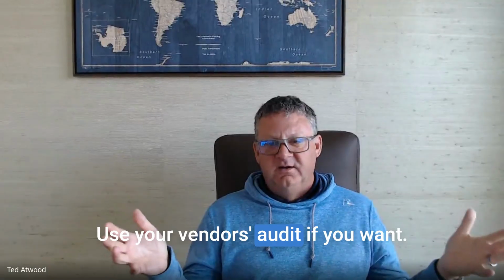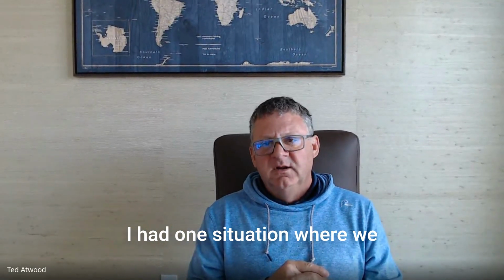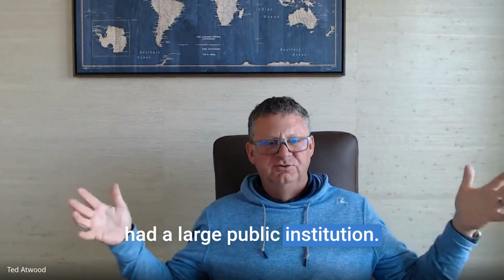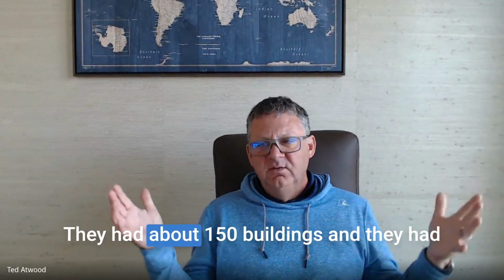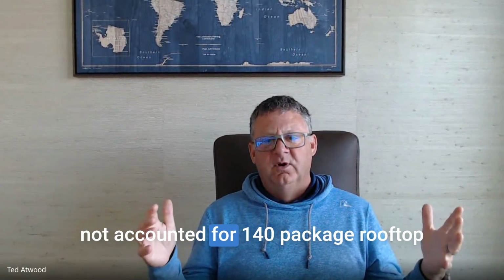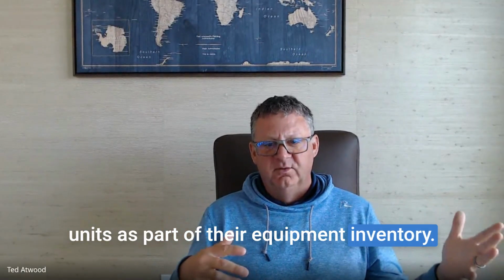You use your vendor's audit if you want. You start with that. Say, okay, we've got your list. I had one situation where we had a large public institution that had about 150 buildings, and they had not accounted for 140 packaged rooftop units as part of their equipment inventory.